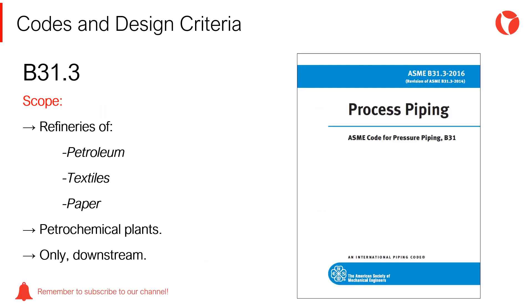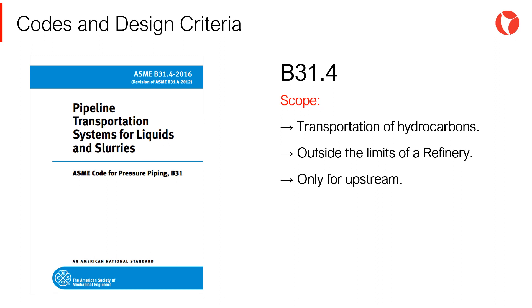The piping design code ASME B31-3 is applicable to the design of refineries — petroleum refineries, textiles, paper refineries — as well as petrochemical plants, and only for downstream plants. The piping design code ASME B31-4 is applicable to the transportation of hydrocarbons outside the limits of a refinery and upstream.